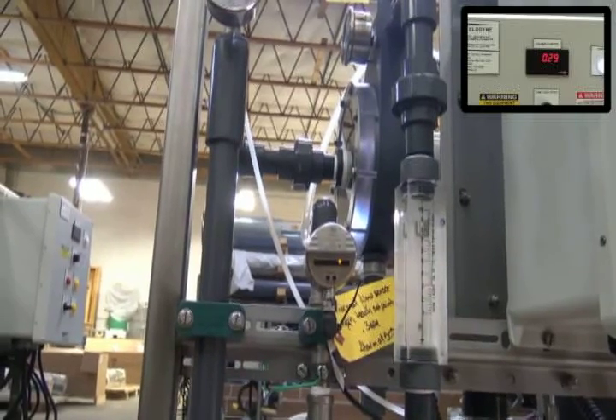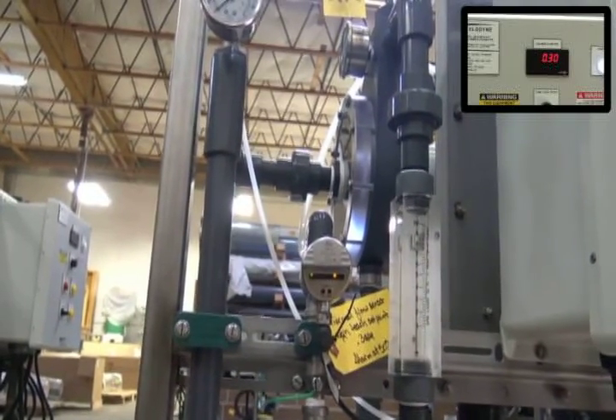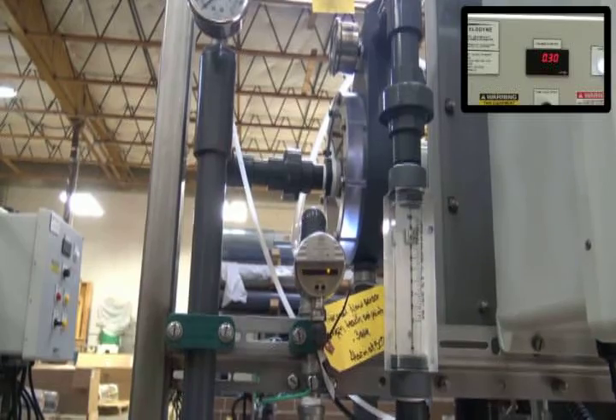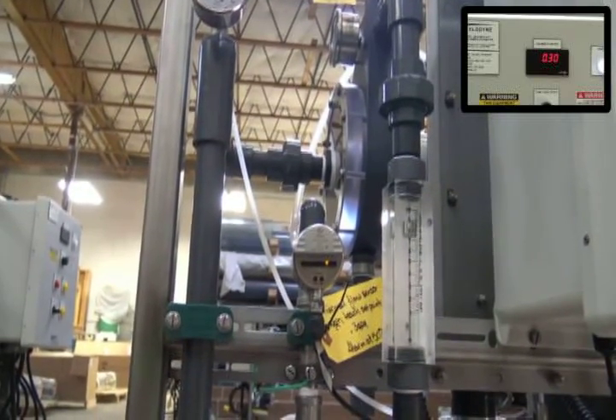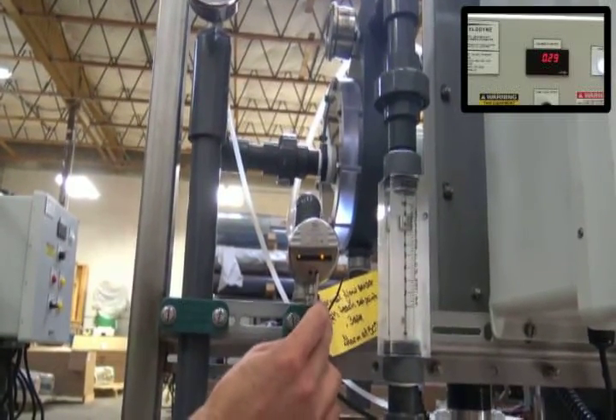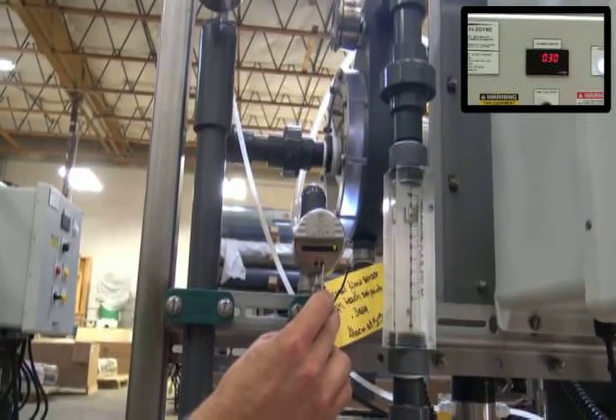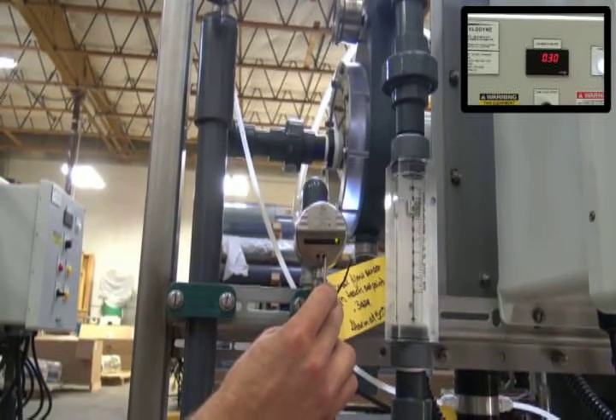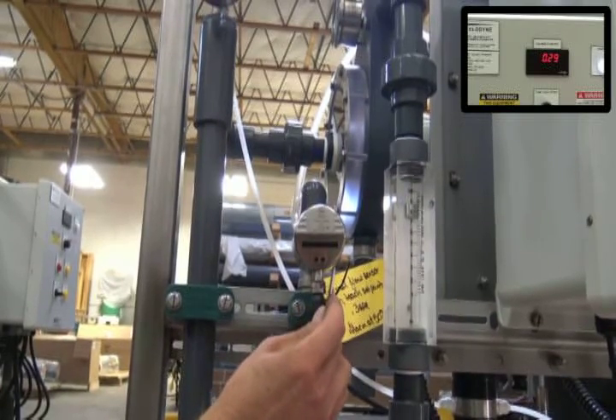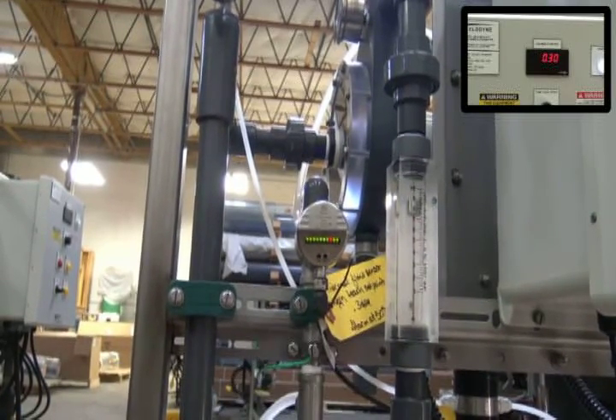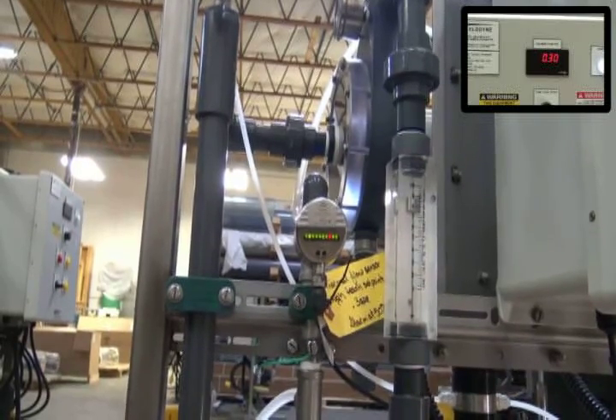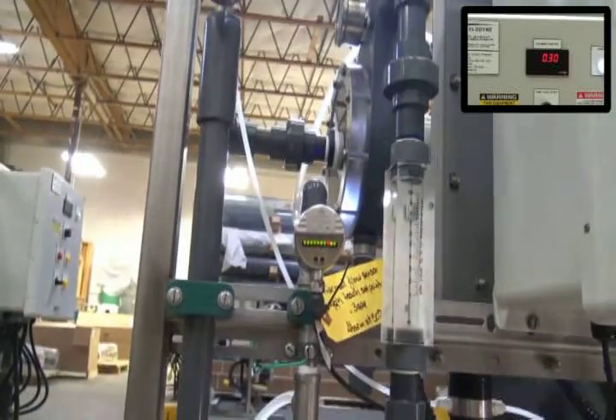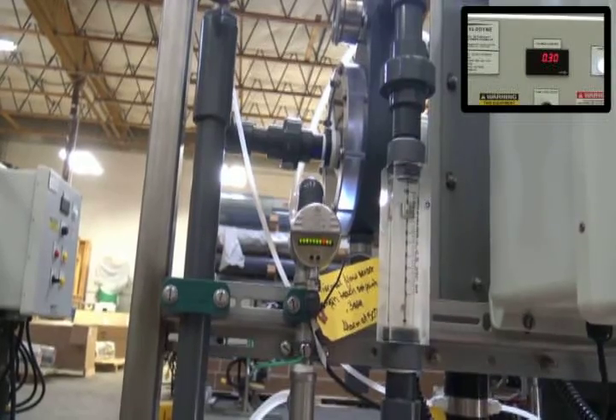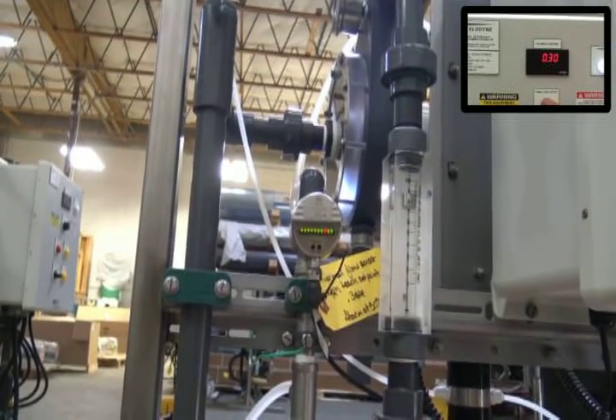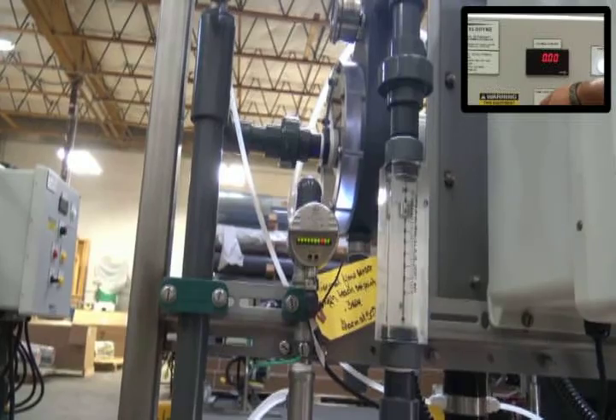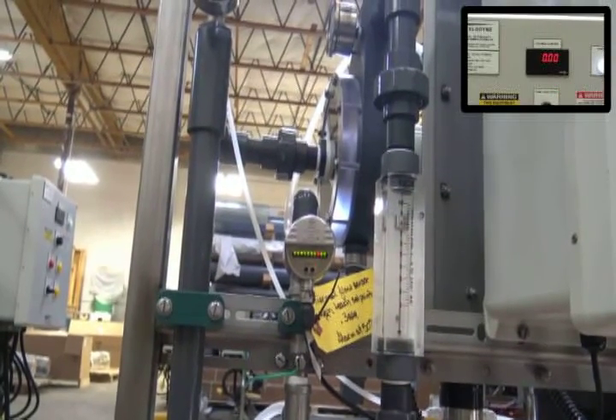But now we're at 0.3 still, and we've been running for a little while. So now we're going to go ahead and do our high teach on this thermal flow sensor. See the green light go solid, it'll start flashing, and let go. You've just done your high teach set. So now at this point we would bring this down to 0. On your system it will be a little bit different if you know your numbers, but if not, then you just bring this down to 0 so we can do our low teach.